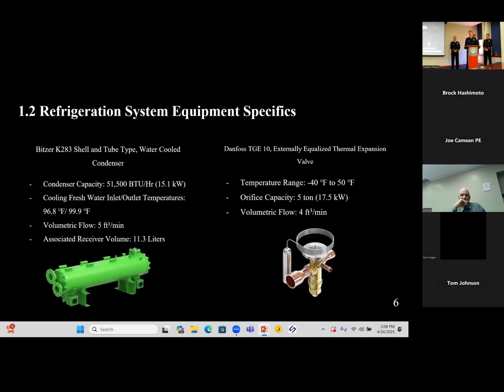Next up, we selected a Bitzer shell and tube type freshwater cooled condenser. This condenser has a capacity of 51,500 BTUs per hour, utilizes cooling freshwater from the freshwater cooling system, a volumetric flow rate of 5 cubic feet per minute, and a receiver volume of 11.3 liters.